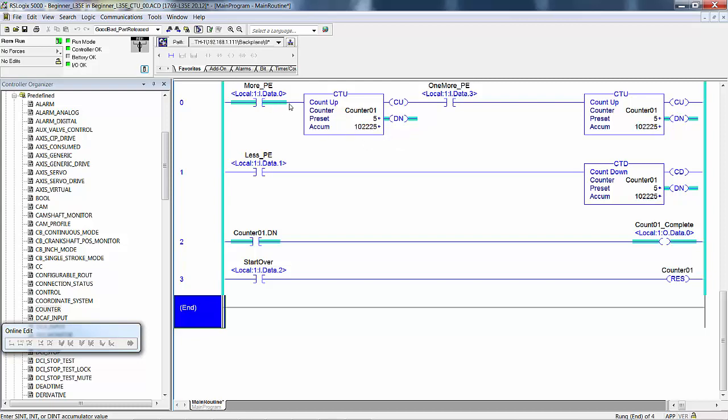So this true out initiates a count up bit, but then this is false. The false execution resets this. Next scan around, this is true, counts. False, resets it. So this rung is resetting this counter. It's resetting the false to true state, not the count value.